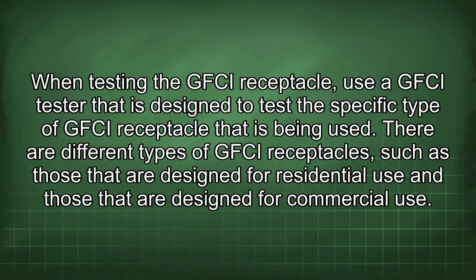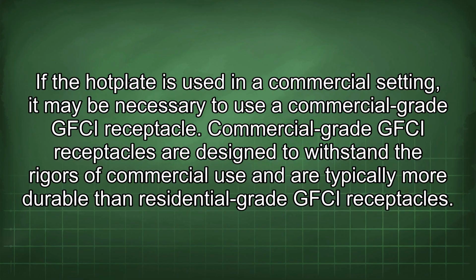When testing the GFCI receptacle, use a GFCI tester that is designed to test the specific type of GFCI receptacle that is being used. There are different types of GFCI receptacles, such as those that are designed for residential use and those that are designed for commercial use. If the hotplate is used in a commercial setting, it may be necessary to use a commercial-grade GFCI receptacle.